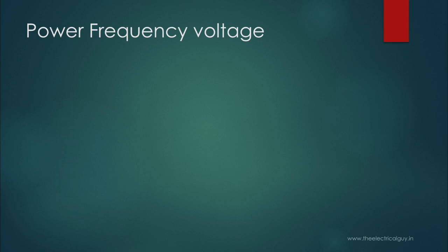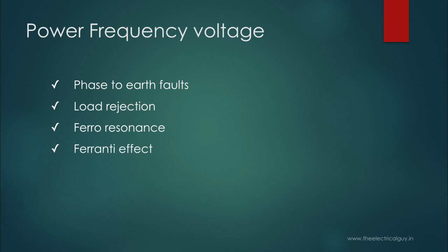Power frequency voltages can be generated due to phase to earth faults, load rejection, ferro resonance and Ferranti effects. Your transformer should withstand this voltage so that the insulation of the transformer remains healthy even in this kind of situation.